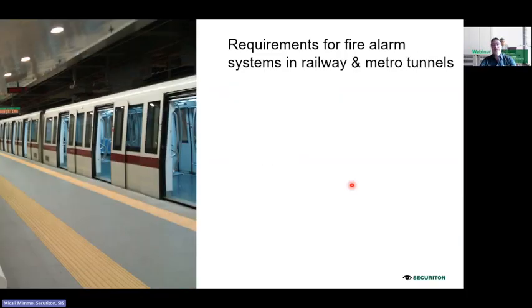Then there are also requirements for railway tunnels or metro tunnels. Most of them are similar, but here we also have different conditions. Wind is of course a topic. We have trains entering a tunnel at speed, and this will additionally increase the wind inside, the piston effect we have inside the tunnel. We have metallic dust from the railway tracks when the train is braking also. So a lot of metallic dust in the air can also cause problems to a system. Then we have the electromagnetic field caused by the power cable, where usually 16,000 to 24,000 volts are used inside the tunnels. And so the system must also be immune to this kind of electromagnetic field.